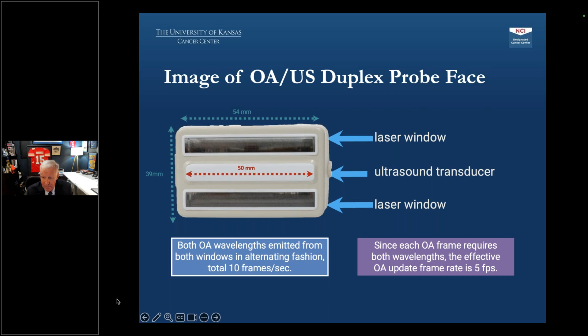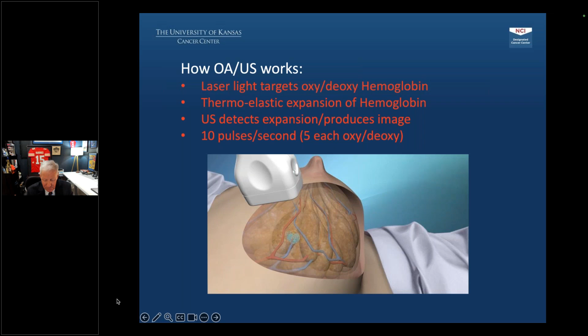This is a brief video representation of what happens with OA. We fire 2 laser pulses that cause thermoelastic expansion of the blood vessels, which creates a pressure wave back to the ultrasound probe, which it detects. This takes about 200 microseconds. There are 10 laser pulses fired per second, 5 on the short wavelength and 5 on the long wavelength. So since you need a long and short wavelength to create a single frame of OA, the actual update rate of OA is 5 frames a second.